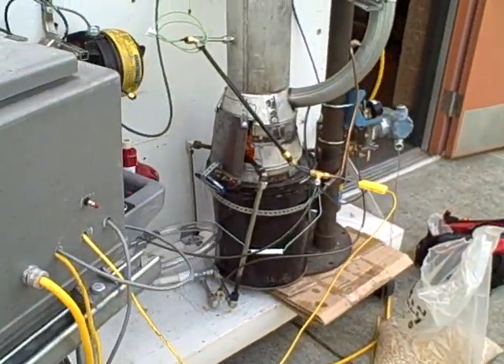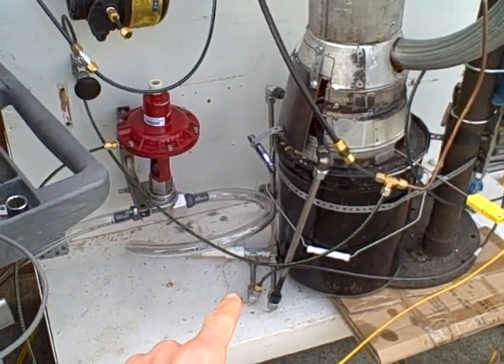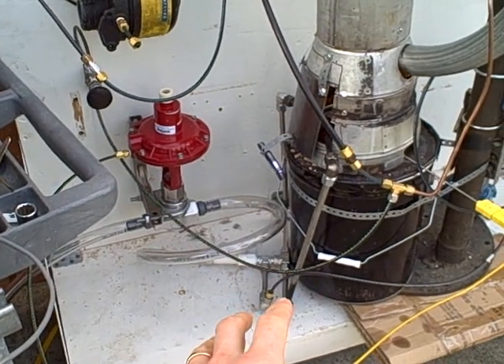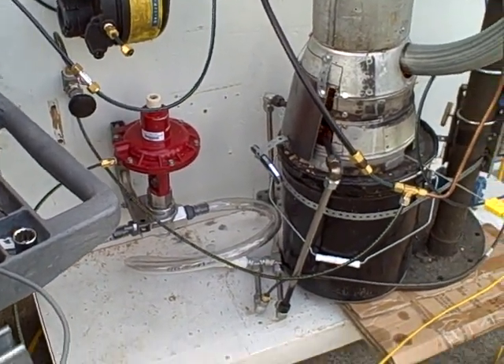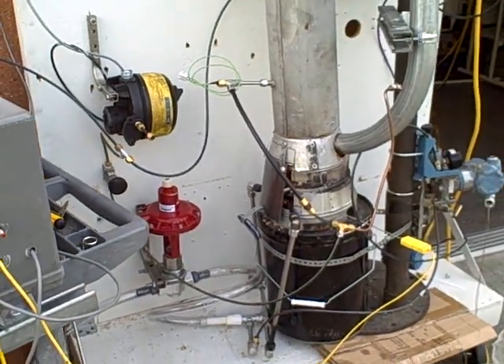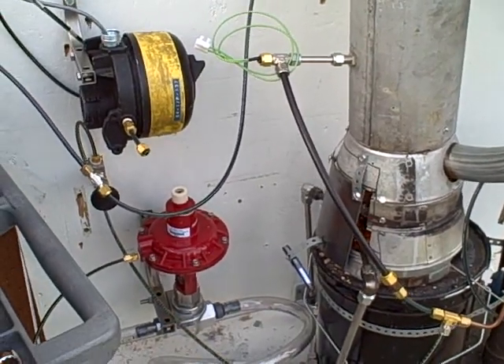So we're doing a simple PID control on it right now. Later on, we're going to add a pressure transmitter to our fluidizing line to measure pressure and have that be a cascade slave loop to the temperature control master loop. Lots of fun on this project, lots of progress to be made. We're just getting started here, and we'll have fun with it over the next week.